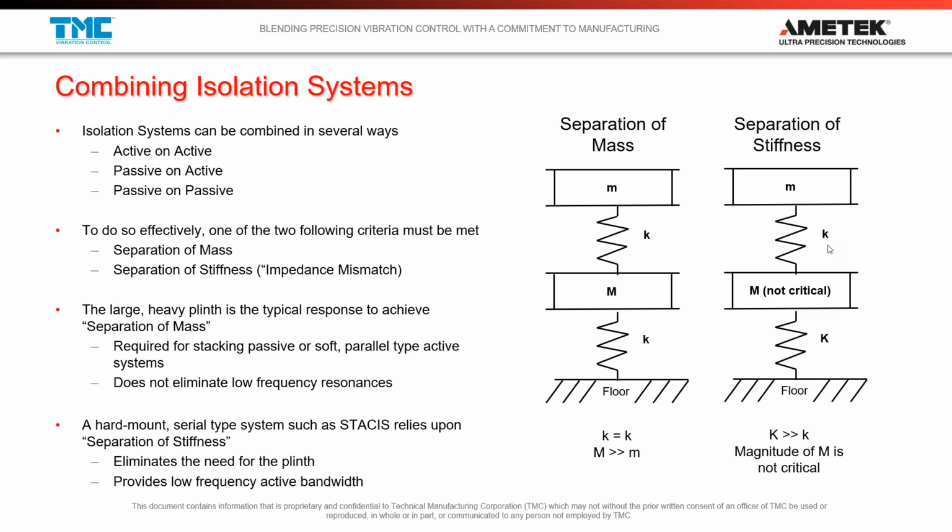And then you get another summing of the transfer functions. You get the resonance of this soft spring, and then its isolation, but then you get the lack of resonance of the stiff spring active system, for example, and then you get summing of the transfer functions and less of a roll off at higher frequencies.